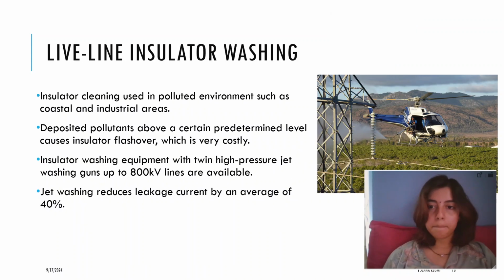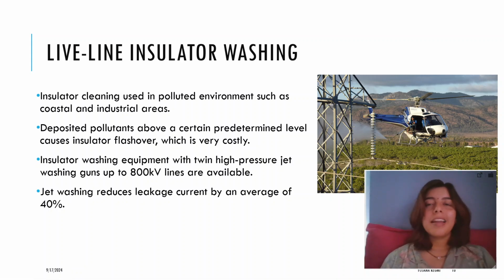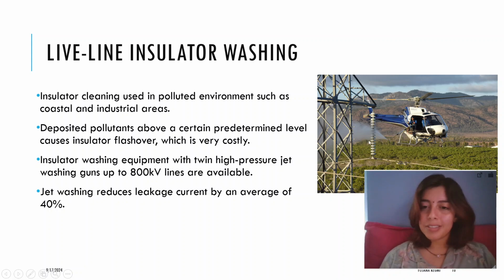Now this is live line insulator washing. This is an exciting part for me. Why do we need to wash the insulator? An insulator is a non-conducting device, obviously, and you can see there is a transmission tower and this insulator stacked one on another. This is clearly a suspension type insulator on a suspension type transmission tower, and the conductor is connected at the end. It is not supplying, it is actually holding the conductor.